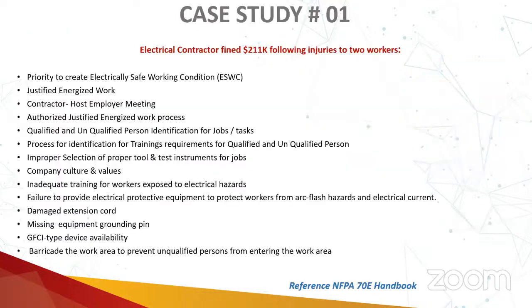Right. So if the things suggested by NFPA 70E had been followed, this incident would have been prevented. 70E always talks about creating an electrically safe work condition before performing any task. If this task had been performed after establishing an electrically safe work condition, then even with the other things they did wrong, like the usage of insulated tools or XYZ, this incident could still have been prevented. But the first thing was to establish an electrically safe work condition. If the task is performed on the live state, it needs to be justified.